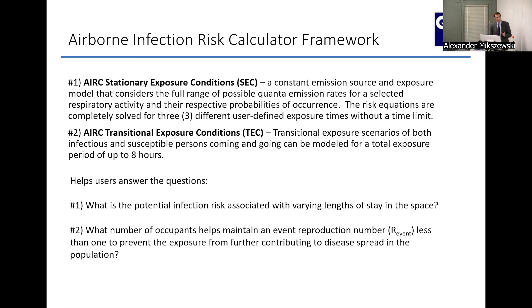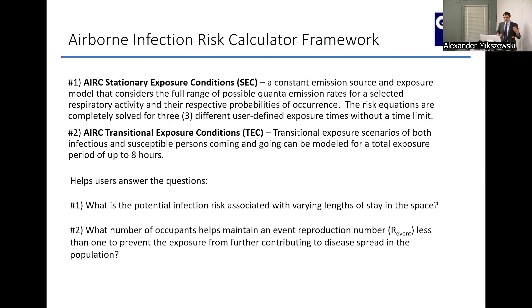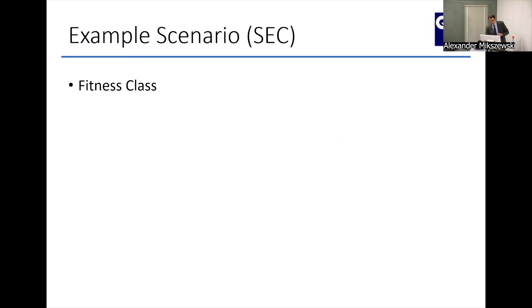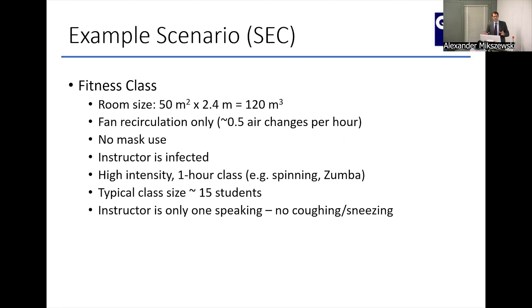The two main questions this tool was intended to answer: the infection risk for different exposures in that space — but that is very abstract. Saying 'your infection risk is 3%' is very hard for people to absorb and use as an actionable indicator for decision-making. More useful, we found, was the number of occupants such that an infection would not be expected on average — statistically, you would not expect secondary transmission with this ventilation rate, this activity, and this number of occupants in that room.